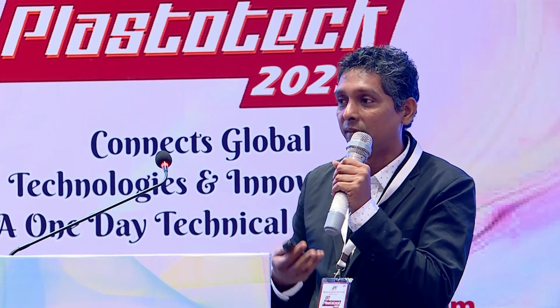So this is our green thumb pipe, you have already seen. Scaling is a very big issue for cooling towers, right? Even if you use plastic pipe, we are unable to avoid scaling. Scaling happens because of evaporation in the cooling tower. But with PP pipes, descaling is very easy. We can do high pressure acid cleaning even after 3 or 5 years. The pipe will not be affected because PP is a chemical resistant pipe, and the joints will not be affected by the high pressure. So you can safely do descaling with a PPR piping system.